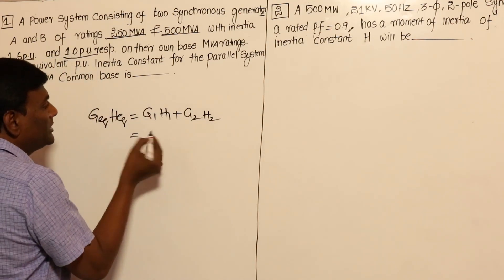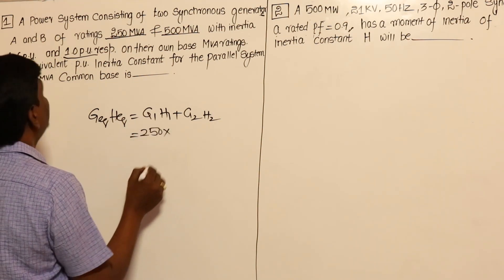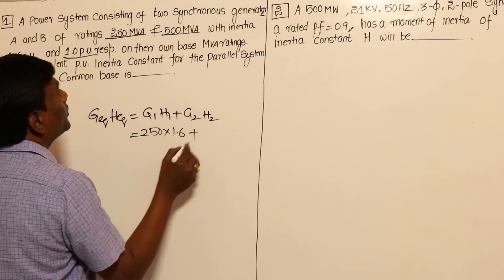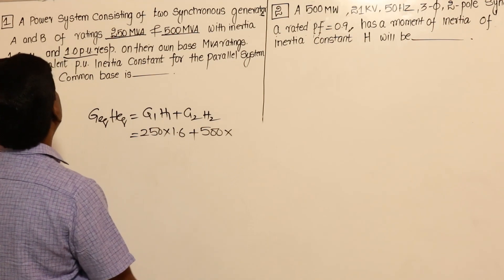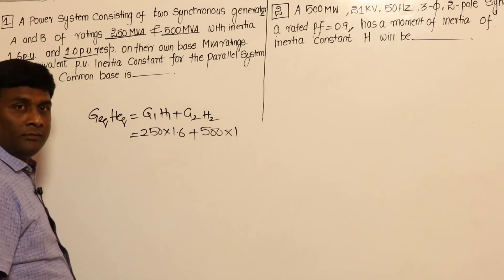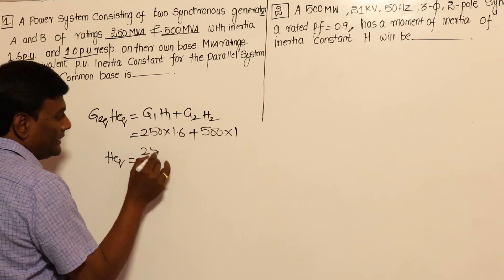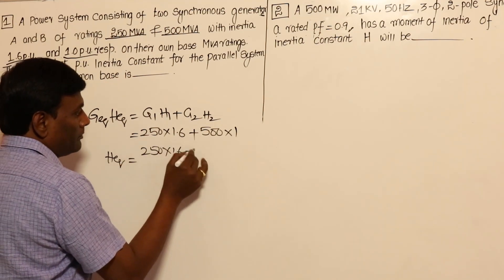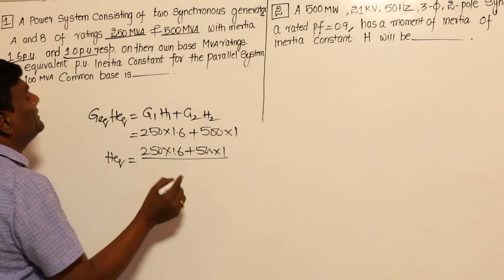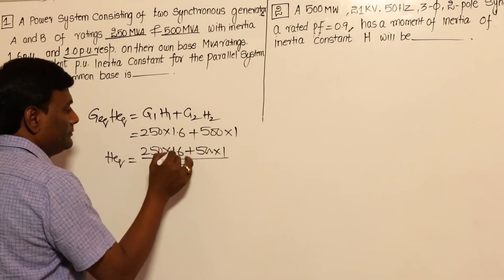So G1×H1 = 250 MVA × 1.6, plus G2×H2 = 500 MVA × 1. Then H_equivalent = (250×1.6 + 500×1) divided by G_equivalent, which is 100 MVA. I got 9 per unit.